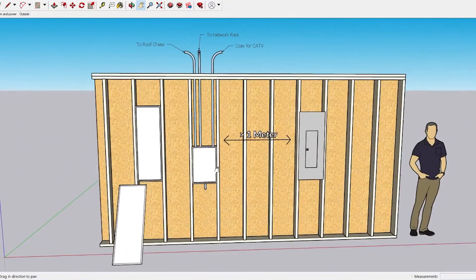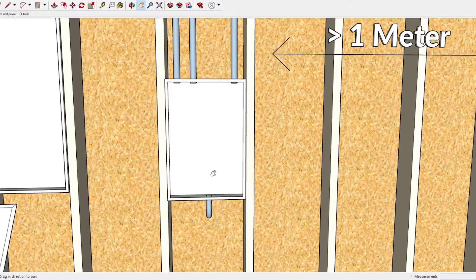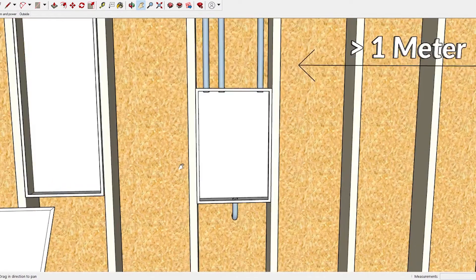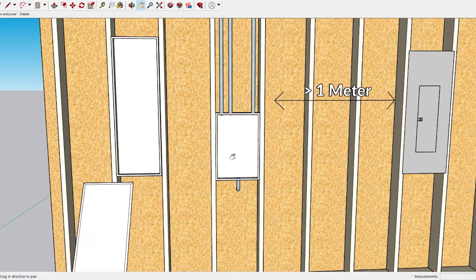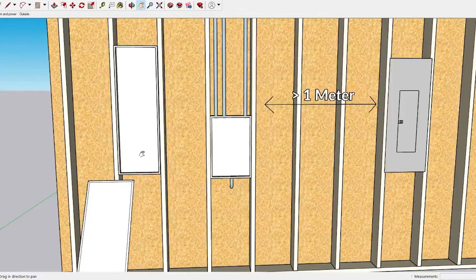Here's a quick tour around this minimum point of entry sample. We've got three portions: this interior Leviton low voltage box — a 21-inch Leviton box here, though there are many manufacturers like Legrand and Commscope. They come in two major types: a powder-coated steel enclosure with either a hinged or screw-on cover. They also come in multiple sizes — the one mocked up here is 21 inches, and over here for size comparison is a 42-inch. The 28-inch is seemingly the most common size.